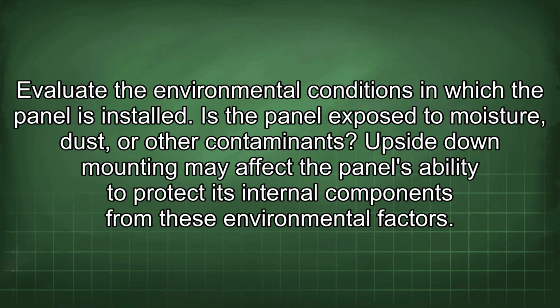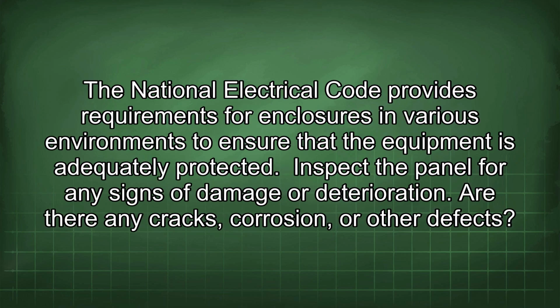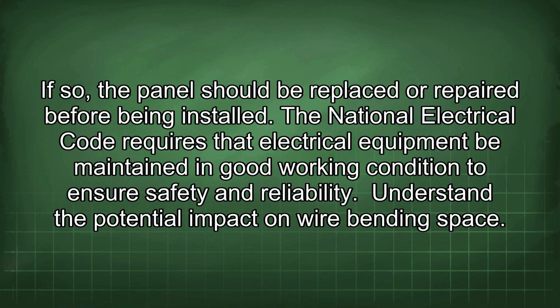Evaluate the environmental conditions in which the panel is installed. Is the panel exposed to moisture, dust, or other contaminants? Upside-down mounting may affect the panel's ability to protect its internal components from these environmental factors. The National Electrical Code provides requirements for enclosures in various environments to ensure that the equipment is adequately protected. Inspect the panel for any signs of damage or deterioration. Are there any cracks, corrosion, or other defects? If so, the panel should be replaced or repaired before being installed. The National Electrical Code requires that electrical equipment be maintained in good working condition to ensure safety and reliability.